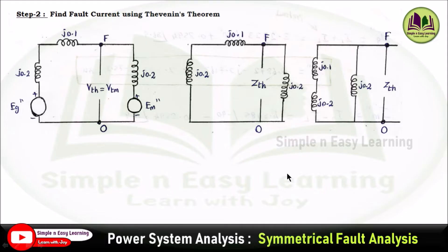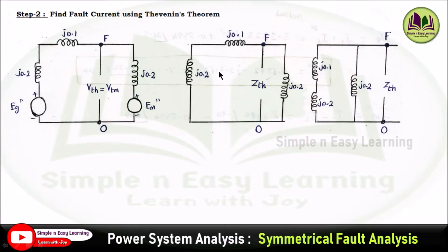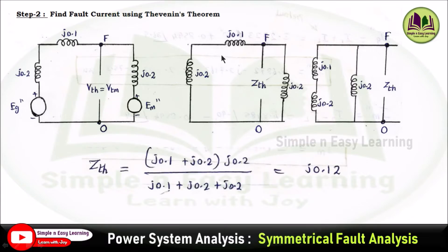Step 2: Draw the Thevenin equivalent circuit at the fault location. From the single line diagram equivalent circuit with generator, transformer/line, and motor, you need to obtain Z_Thevenin at the fault point. The fault point is a node; the impedances to the left (j0.2 and j0.1) are in series, and this series combination is in parallel with j0.2 on the motor side. Calculating: (j0.1 + j0.2) × j0.2 divided by (j0.1 + j0.2 + j0.2) gives Z_Thevenin = j0.12.